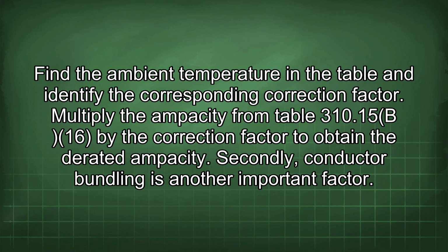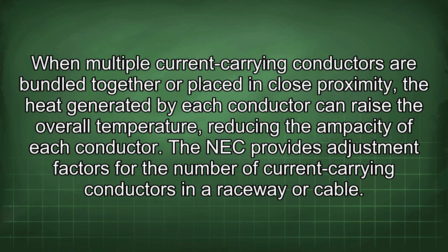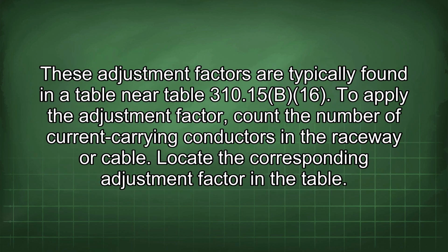Secondly, conductor bundling is another important factor. When multiple current-carrying conductors are bundled together or placed in close proximity, the heat generated by each conductor can raise the overall temperature, reducing the ampacity of each conductor. The NEC provides adjustment factors for the number of current-carrying conductors in a raceway or cable.